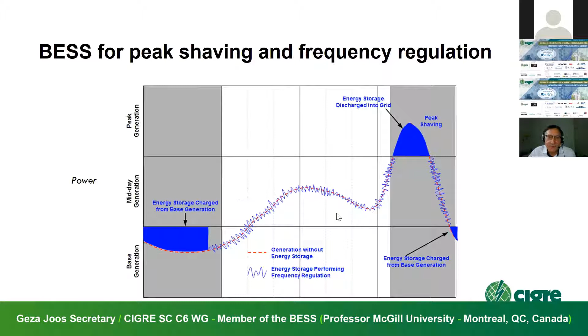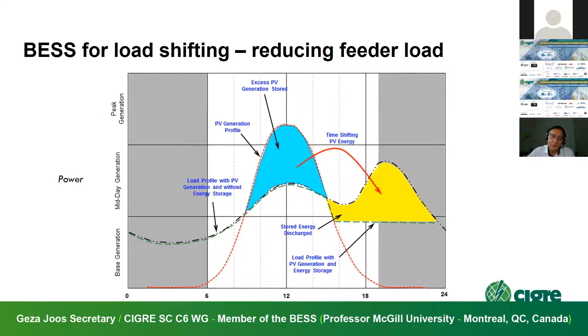This is another application that has been tried in Canada and the US. When you have an overloaded substation, you can add batteries to supply the load for the short term, such as morning and afternoon peaks, which may justify the use of a battery energy storage system. The only problem is that if the substation load increases in the future, this is just a short-term solution.